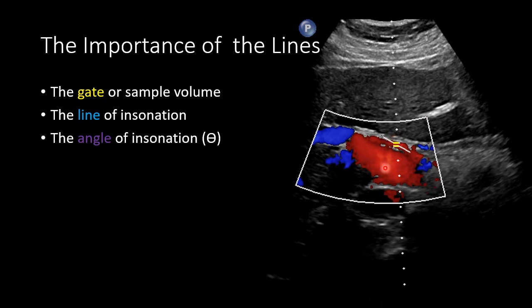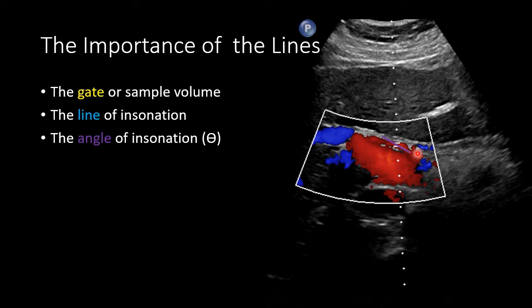In addition to the gate outlined in yellow, we will have the line of insonation. This is a representation of the direction that our ultrasound waves are traveling in. Realize that the motion that we are trying to measure is not necessarily traveling in parallel with our ultrasound waves. Because they are not traveling in parallel, we need to angle correct to determine the angle of insonation. We angle correct with a user-defined line that is typically a small white line I have now highlighted in purple. We adjust that white line to reflect the expected direction of movement or motion or flow within the gate.